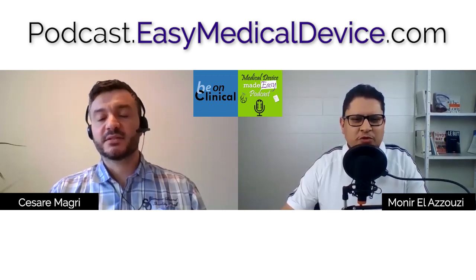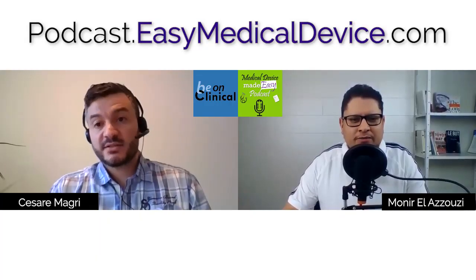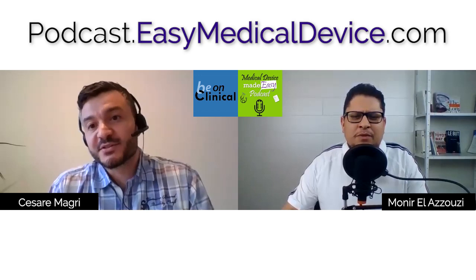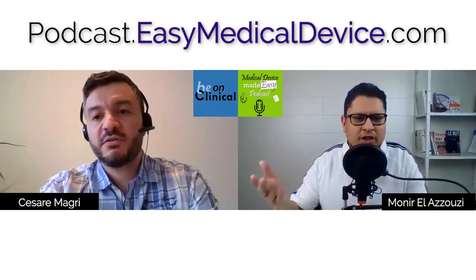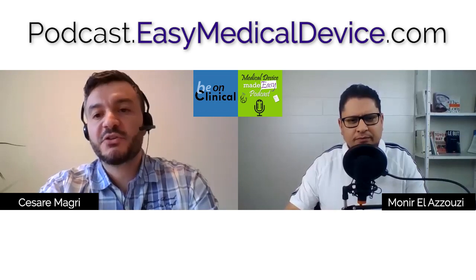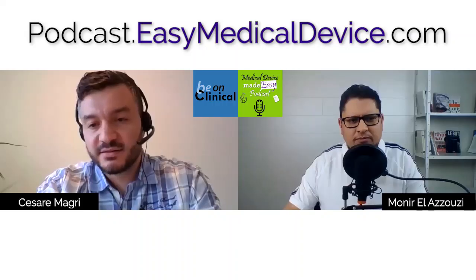So it means that you used it as you wanted, or you thought that it could work that way, but it's not something that the manufacturer is recommending. Exactly, and at that point the manufacturer is also not legally responsible. Exactly, in case something happens, which is really very important. But I saw also that for clinical evaluations, for PMCF, you also have to collect off-label use if you are seeing that. So even if you are not writing that, you may collect it just to see for which other purpose your device was used, even if it's off-label. Yes. So if you see that it's commonly also used for treating something else, you should note it down and think of whether it's necessary to collect data for that.